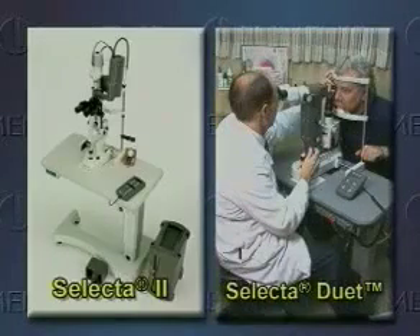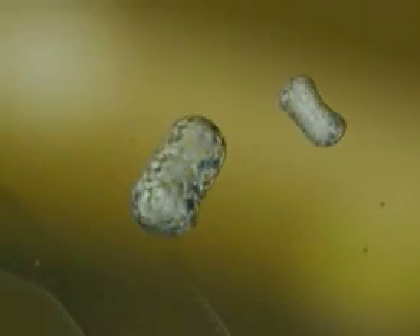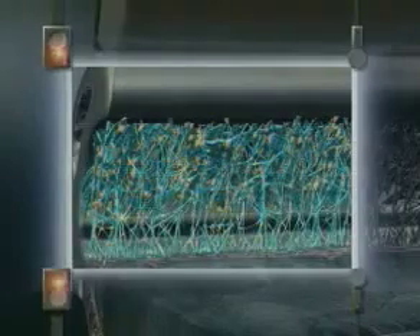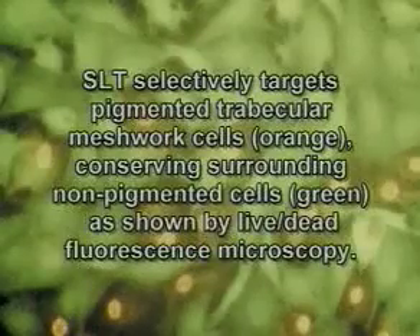The Selecta Duet offers a new combined laser system with the option to treat glaucoma or secondary cataracts. SLT is based on selective photothermolysis — the process of targeting a specific cell and confining thermal laser energy to that target. This minimizes collateral damage to surrounding tissue. SLT using the Selecta specifically targets melanin-containing cells in the trabecular meshwork to lower intraocular pressure.